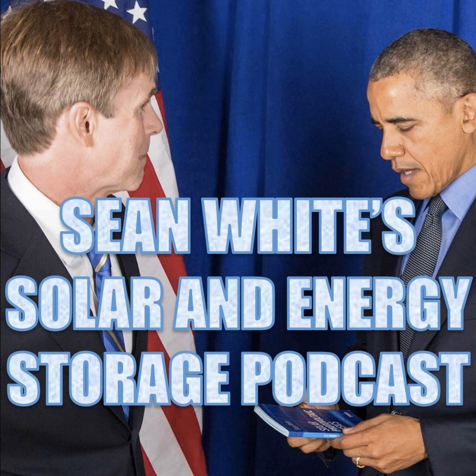So our first question is going to be about grounded versus ungrounded inverters. And so let me say one more thing about that too. Way back in the 2014 National Electrical Code, and previous to that, we had these different terms for inverters, which we called grounded and ungrounded inverters. Then in the 2017 National Electrical Code, and that means also versions after that, we changed the words. And so now they are all called functionally grounded inverters.